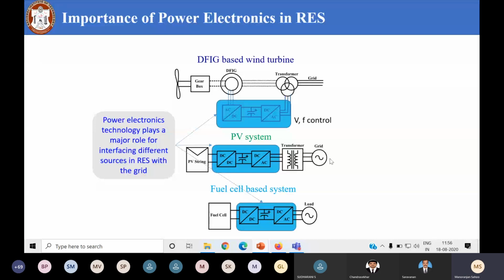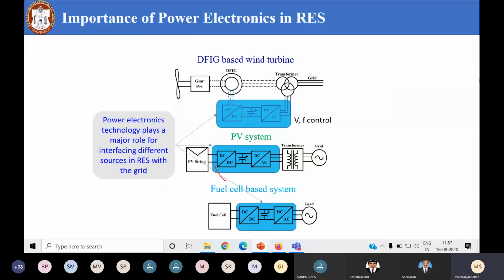But the AC output required is quite high, so to do that you have to use either a boost DC-DC converter, which can act as a boost converter and also serve the MPPT purpose. Similarly, this inverter is for converting DC to AC, because our load here is the grid or an AC load, so an inverter is used for inversion. Now, if people don't use this boost converter, they use a transformer instead, for isolation as well as stepping up the voltage so that it matches the grid voltage. I'll discuss this a bit more in the next slide.